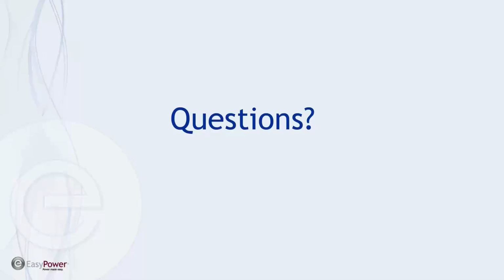The next question is, is the grounding equipment reusable, or does it need to be replaced after the fault? Yeah, these are typically one-shot devices, but we recommend having 3 spares, and that's the reason why: once it operates, you can switch them over to your spares, and you can send the activated devices back to our factory in Ratingen, Germany. We will refurbish them and send them back as your spares. So for a primary solution, we recommend having 3 spares, and once it activates, you can quickly replace them by unbolting on the top of the equipment.